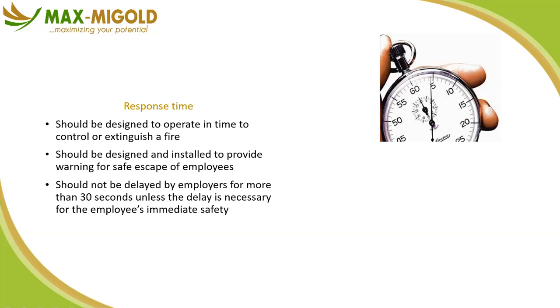What do I mean? You determine the time that it takes to evacuate your building based on historical performance. So you need to carry out drills multiple times, especially if you have not done this before, and you keep timing yourself. So let's say the first time it took about 10 minutes, that's the baseline, but we can work towards a lesser time. Then the next time you have the drill, you do 8 minutes, then 8 minutes becomes your new baseline, until you determine over time the number of minutes it takes for people to evacuate.